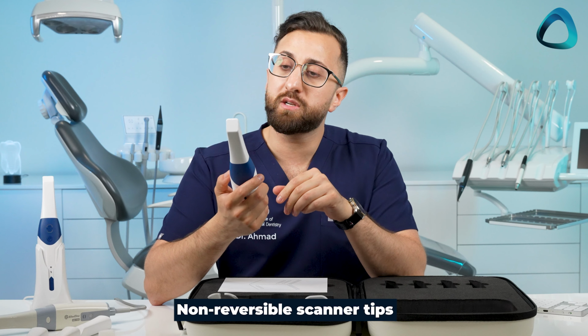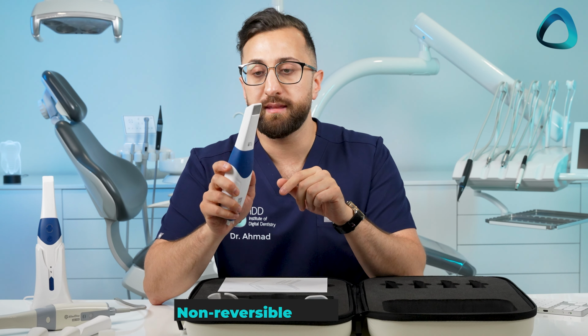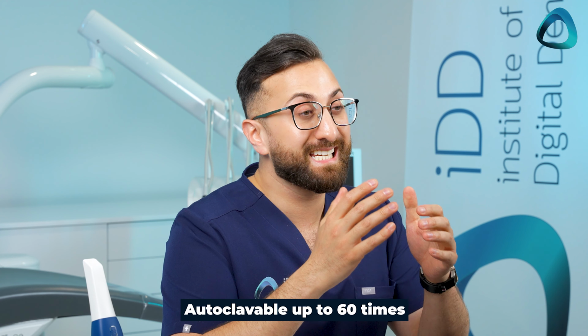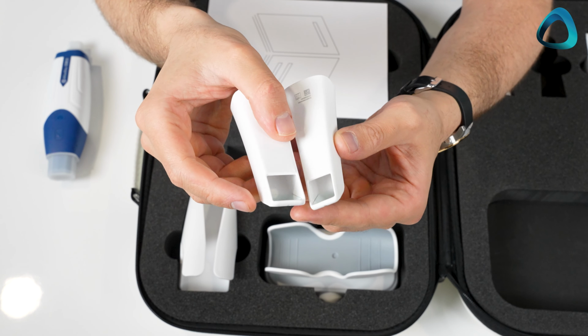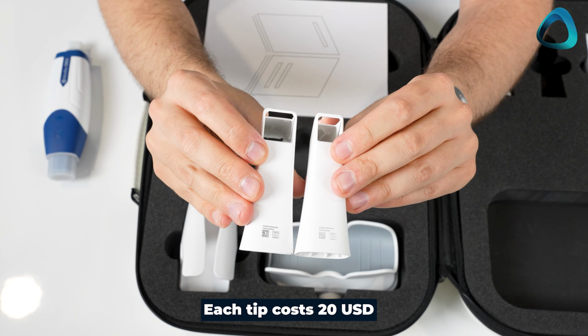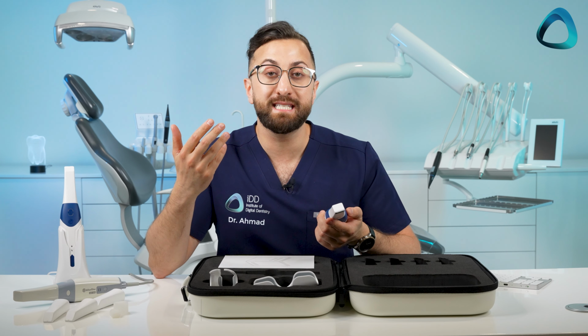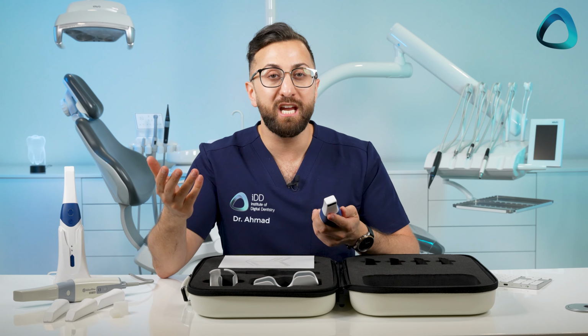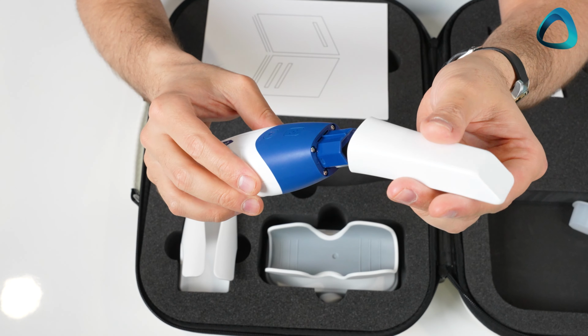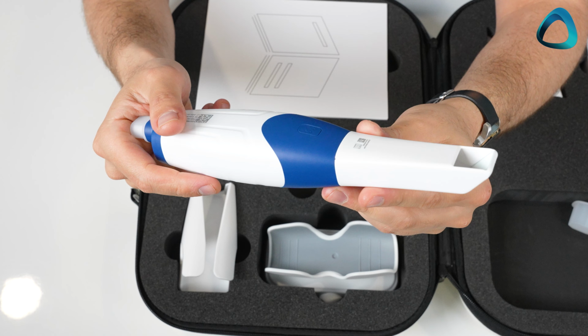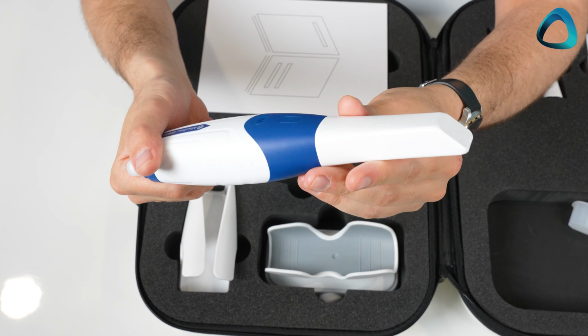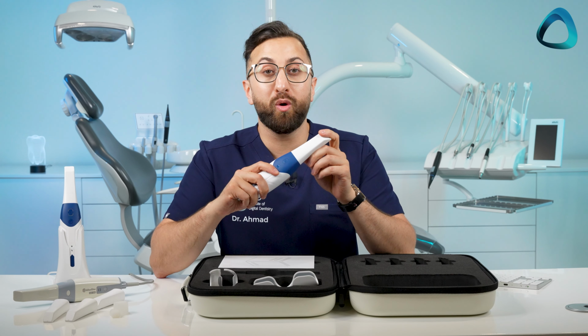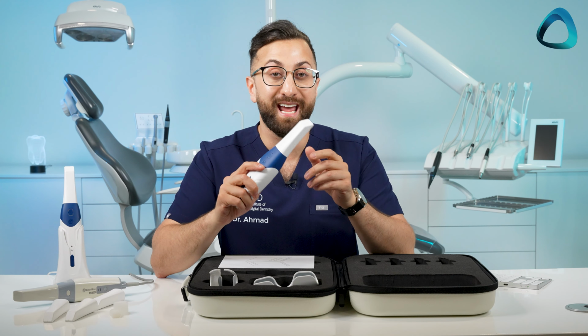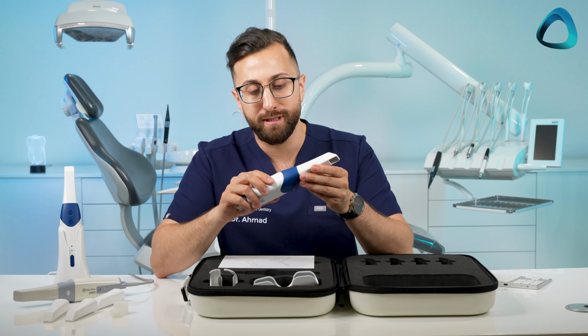And one thing that's quite interesting, I asked the company about these scanner tips and they advised me that they can be autoclaved up to 60 times. The cost of the scanner tip is 20 USD per scanner tip. So that basically means it's about 33 cents per patient, because each patient you're going to be autoclaving them. I have been told, however, that the company is working on newer scanner tips that can be autoclaved up to 180 times. So that is quite interesting.